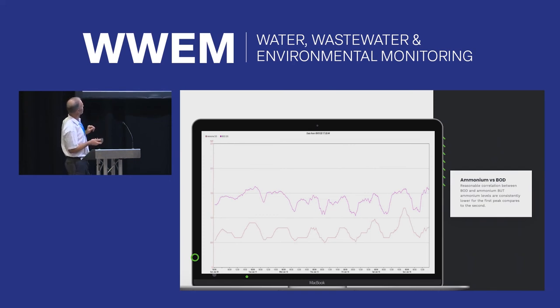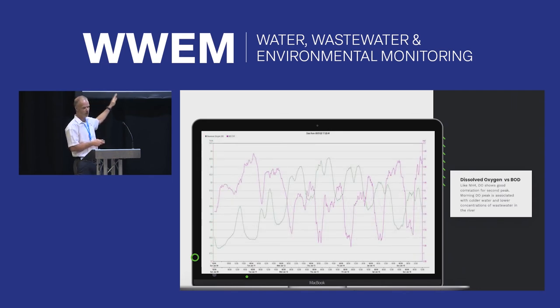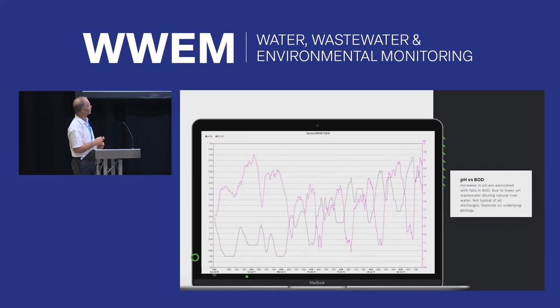So then we started comparing it to the likes of BOD. The great thing about the way we measure BOD is that it's optical, so there's no drift. You'll see later that the ammonia probes drift, whereas the optical BOD will not. You can see here again that you've got the twin peaks on the BOD, but interestingly for this site, the morning peak is much reduced, so we're missing something - is that to do with the process? That was quite interesting.